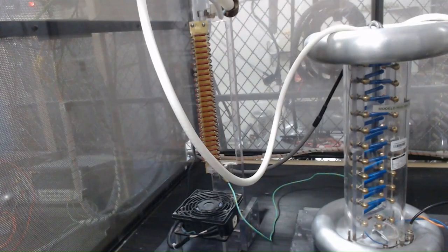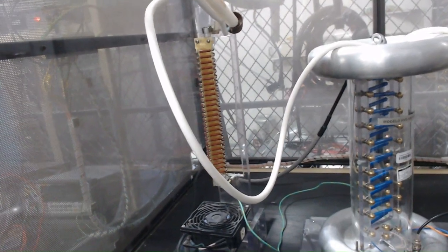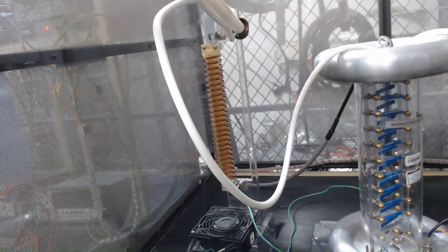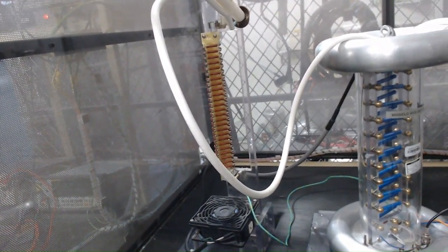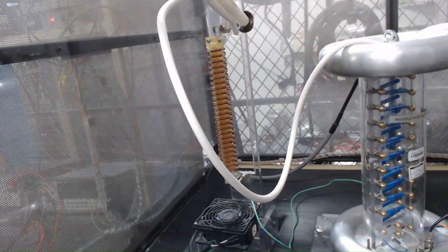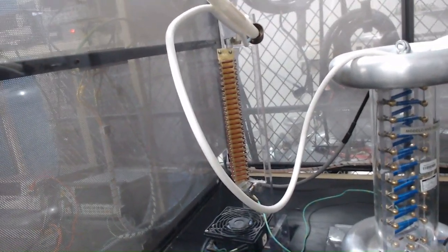In this following test, a lower value resistance load of 10 mega ohms is connected to the output. This is in order to test the X6417 current limit. With the output still set to 50 kV, unit will be powered up. Unit should limit the output such that the output current does not go past 2.2 milliamperes.